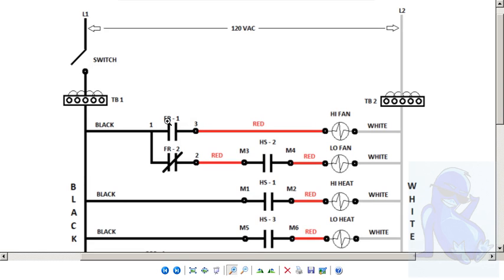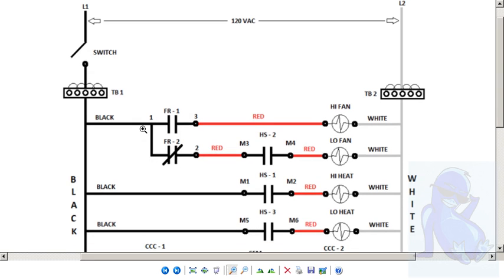looks like it's a fan relay. No, that's not a relay because we are in the high voltage circuit. So this is just the fan 1 and 2. And it's defaulting to 2, which is your low speed fan. Remember that fan relay that showed the 2? This is representing the fan relay, but it's representing the high voltage side. So you've got terminal 1 on your fan relay that we wired into. You have terminal 3 that wires straight to the high fan, high speed. You've got terminal 2 that wires straight to the low speed.